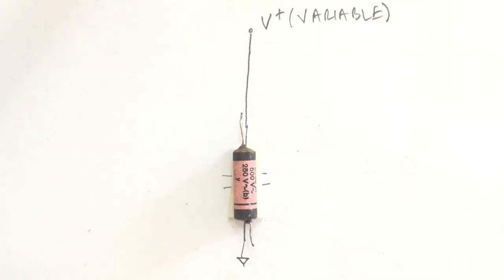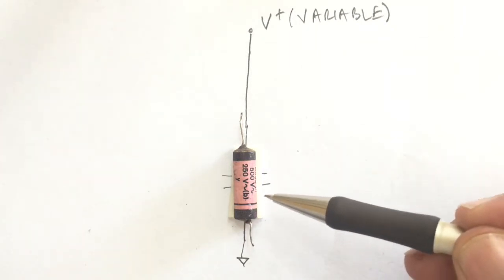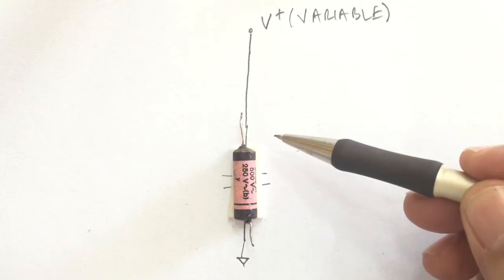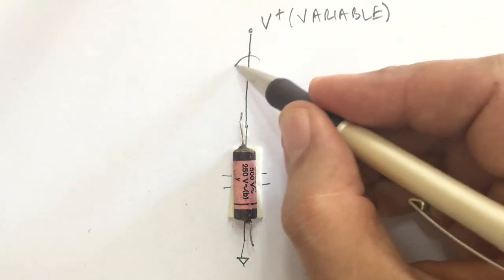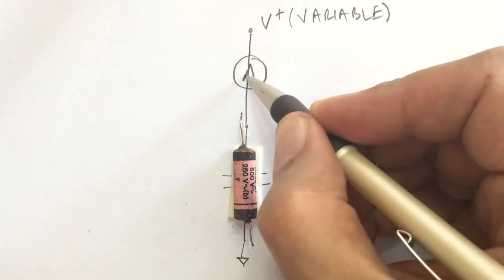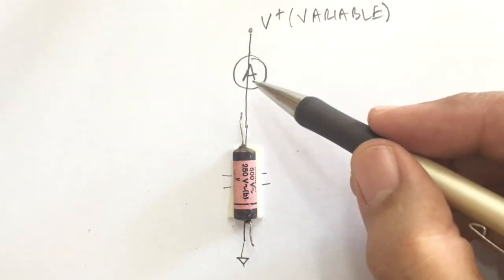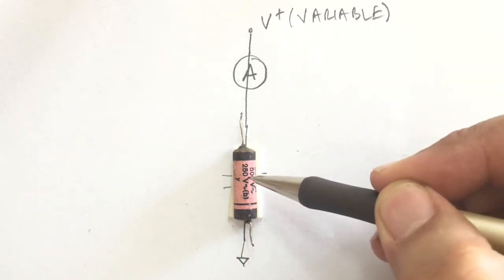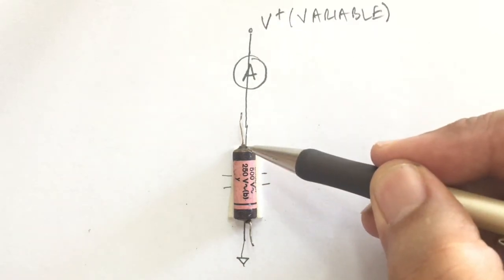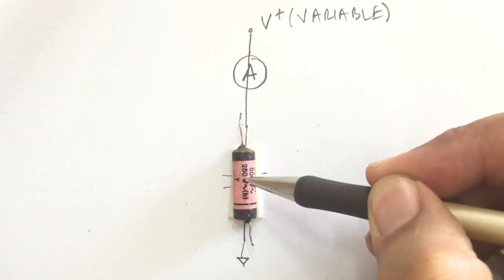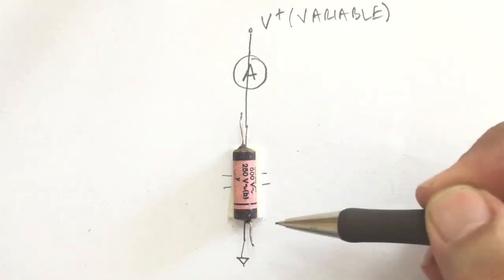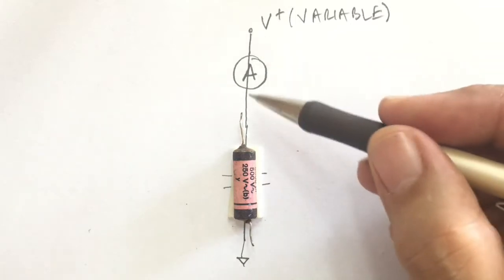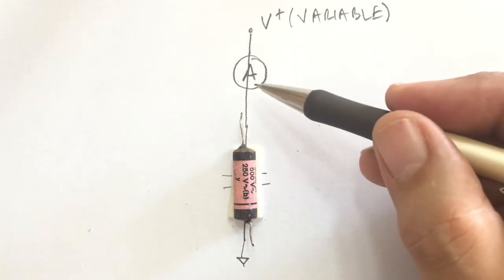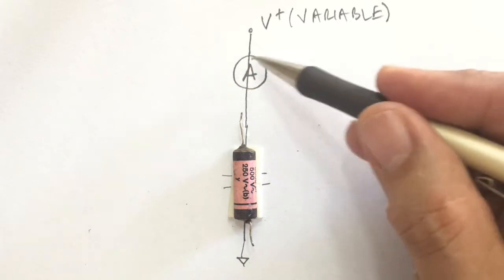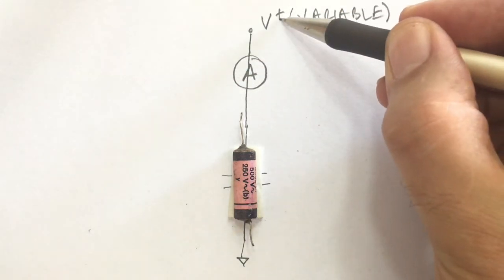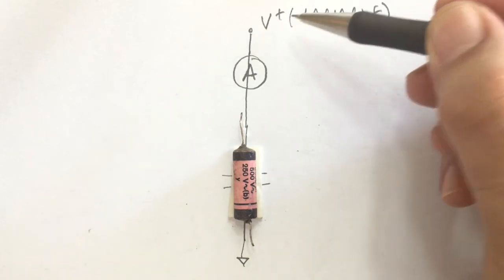Why do you need to vary it? You need to adjust it slowly from 0, preferably, and increase it to measure the leakage current that goes through here with an ammeter. As you increase that voltage, if this capacitor is leaky, the current will increase. If it's not leaky, if it's fine, that current, after the initial charge which draws some current, should be 0. So we're measuring the leakage current for the particular voltage we're applying, which we can vary.